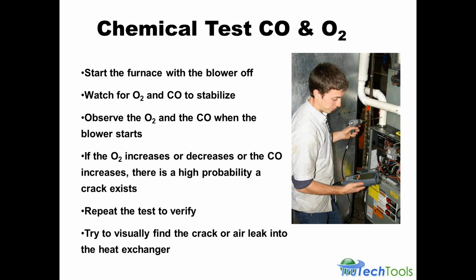Here's a little detail on doing the chemical O2 test, where we start the furnace with the blower off, and then watch for the oxygen and the CO levels in the flue with your combustion analyzer to stabilize. And then as the blower starts to cycle on, very carefully watch the oxygen and CO levels as it starts up. And if the oxygen increases or decreases, or the CO increases, there's a high probability that the blower compartment is talking to the combustion side, which means there's a breach in the heat exchanger. And it'd be a good idea to repeat this test to verify and make sure you've seen those levels. And we're talking about levels in oxygen of about 0.5%, and CO in the range of 50 to 100 parts per million change. So you do have to really take a close look at those readings and make sure that those are changing at those high levels.